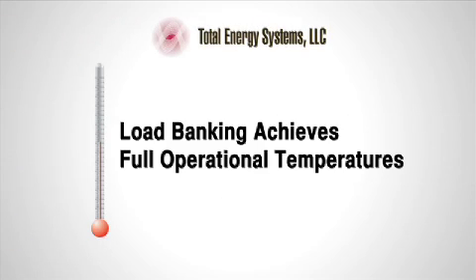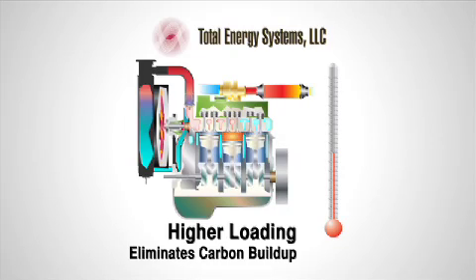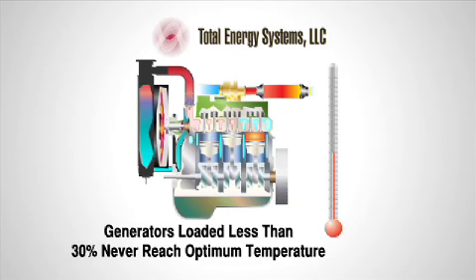Bringing the engine to operating temperature for a period, as defined by NFPA 110, eliminates the buildup of carbon deposits and burns off unused fuel and carbon deposits in the exhaust system, a condition known as wet stacking. Wet stacking is a condition where unburnt fuel and carbon deposits build up in the exhaust system, producing smoke and unnecessary pollution. Generator systems loaded less than 30% never reach the optimum temperature.